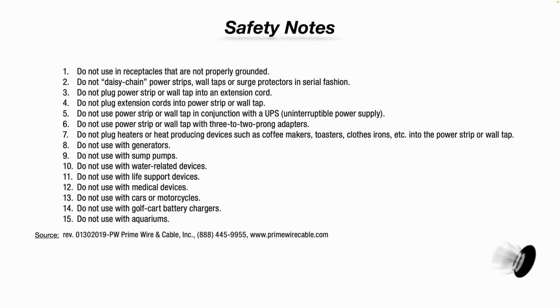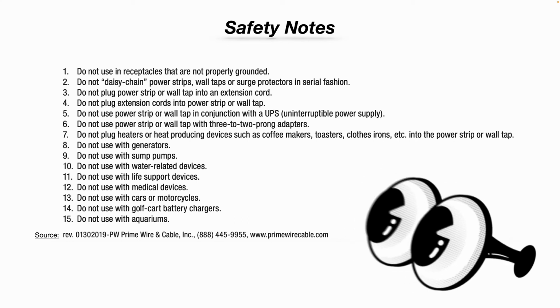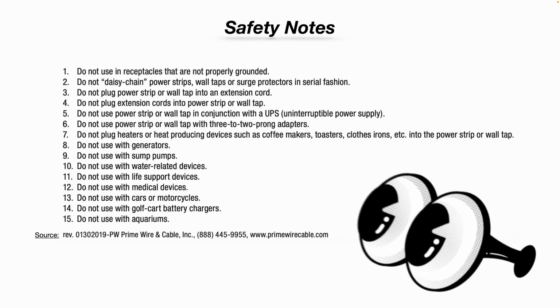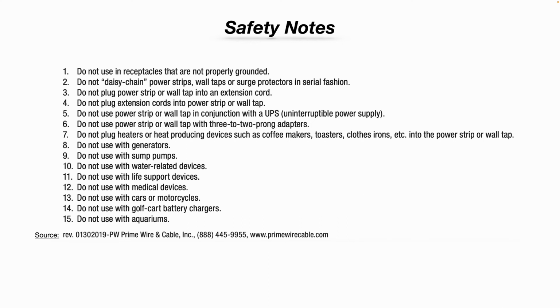And some quick safety notes to go over in regards to extension cords and surge protectors, power strips. Some common sense. Do not use receptacles that are not properly grounded, or sometimes you'll see people cut off the ground prong. That's no good. You never want to do that. Do not daisy chain or hook one power strip into another, or into a surge protector, or into an extension cord. That's not safe. Do not use power strip or wall tap in conjunction with the UPS, which is an uninterruptible power supply. Do not use power strip or wall tap with 3 to 2 prong adapters. Do not plug space heaters or heat producing devices like coffee makers, irons, toasters, etc. into a power strip or wall tap.